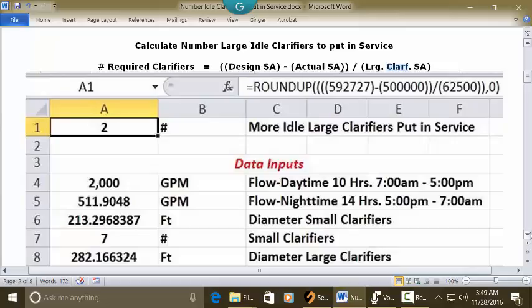Type: =ROUNDUP( with four open parentheses, then 592727, one closed parenthesis, minus sign, open parenthesis, 500000, two closed parentheses, division key, open parenthesis, 62500, two closed parentheses, comma, zero, and one closed parenthesis. Press enter, and in A1 will be your answer: two additional idle clarifiers.